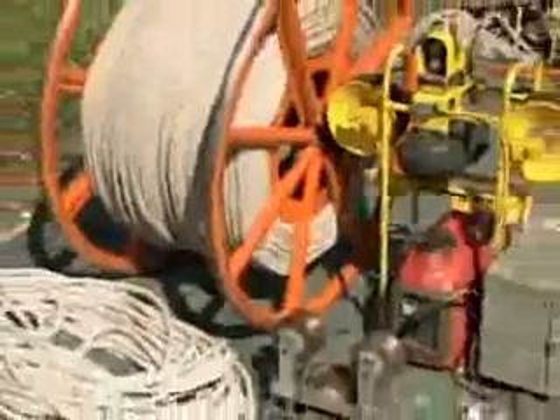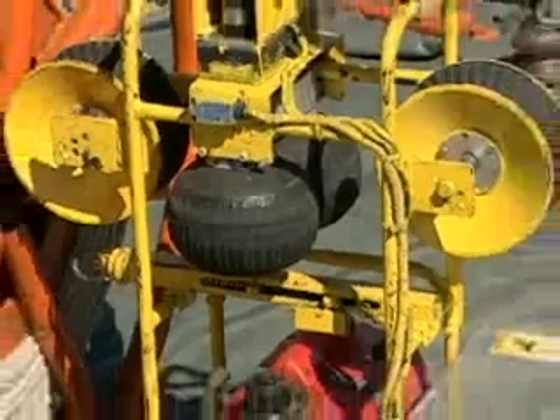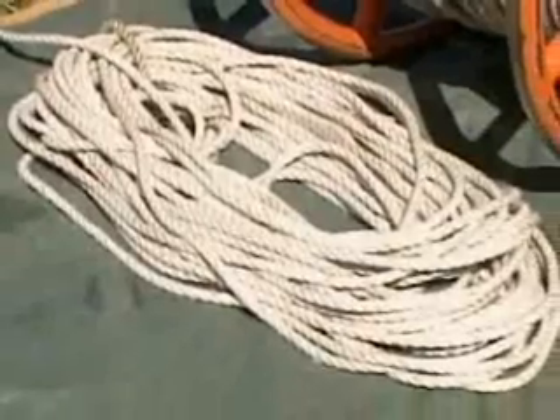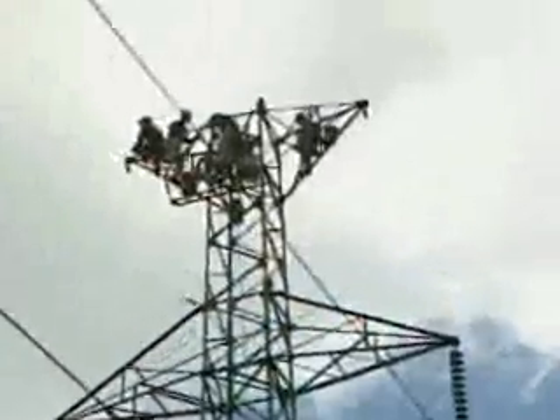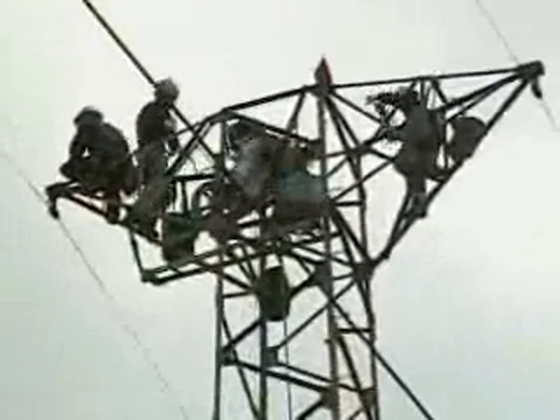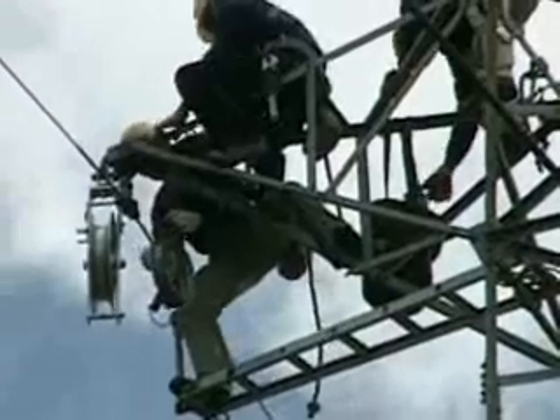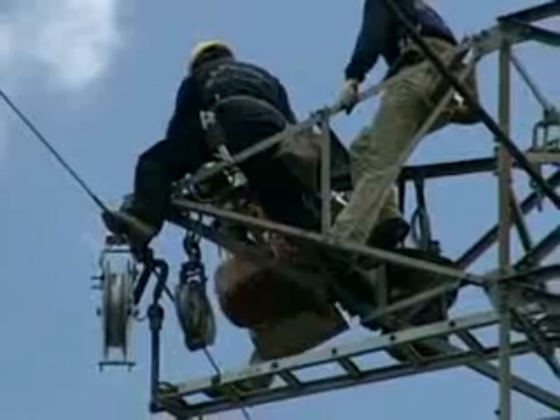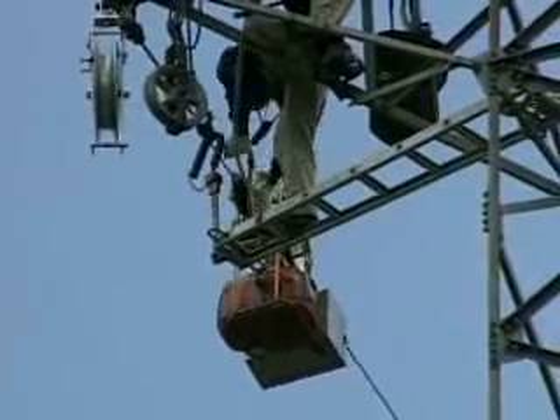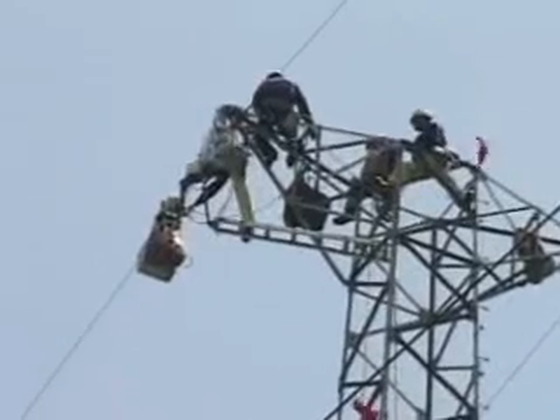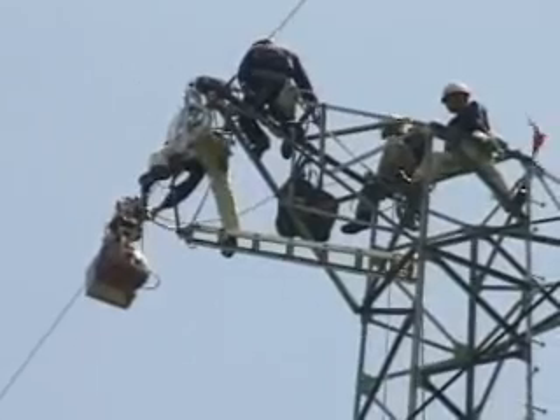Now, the actual procedure of the Furukawa OPGW live line installation method. OPGW live line installation requires few special tools: traction machine, hanging pulley block, insulated ropes, and braking machines. The OPGW live line installation starts by installing pulley block to the cross arm of existing towers. Then the traction machine, which is a compact and light piece of equipment that has been specially made for easy handling, is mounted onto the existing ground wire. Two ropes are attached to the traction machine. One is used to set the hanging pulley blocks on the existing ground wire. The other, which is made of insulated material, will be used to pull the OPGW.